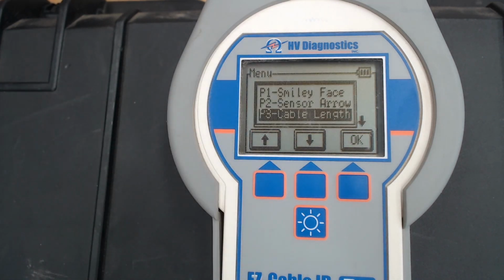Now something to note with pointing the arrow away from the transmitter or towards the transmitter. Let's say, for example, you have it set up to point away from the transmitter. If I point my coil towards the transmitter and I'm on A phase, I will get a negative impulse or a negative signal. I should get a positive signal if my coil is faced the right way. So the fact that I'm getting a negative signal means I have the coil pointed the wrong direction. I can also hit the ID button, that would be this bottom right one when I'm IDing a cable, and it'll show me just having the L1 signal. So when I flip my coil around, it'll then go L1 positive. Same goes for my return.